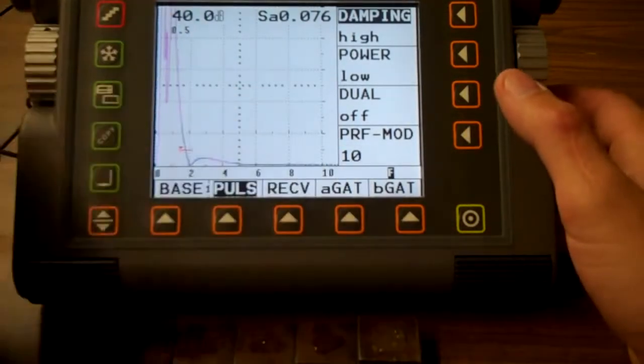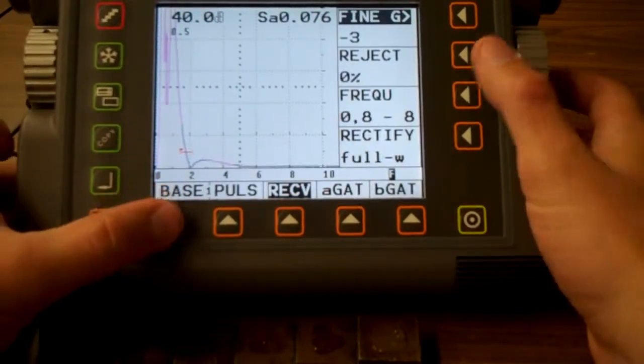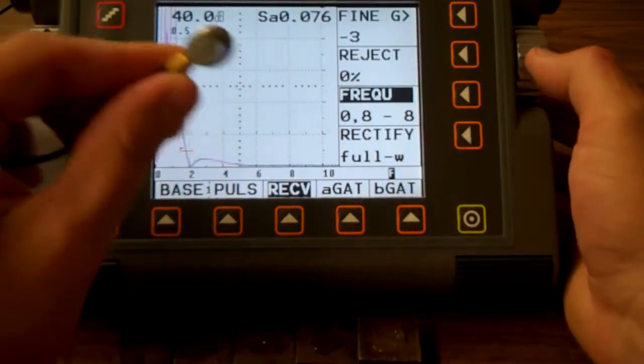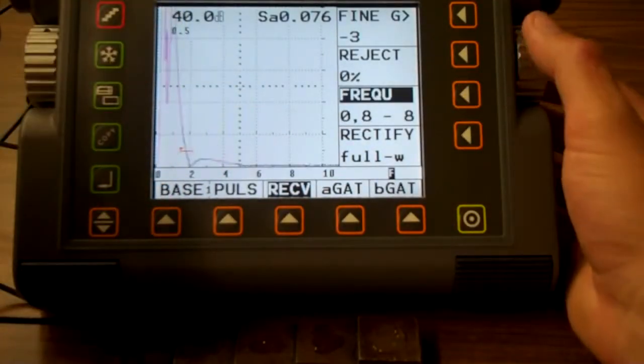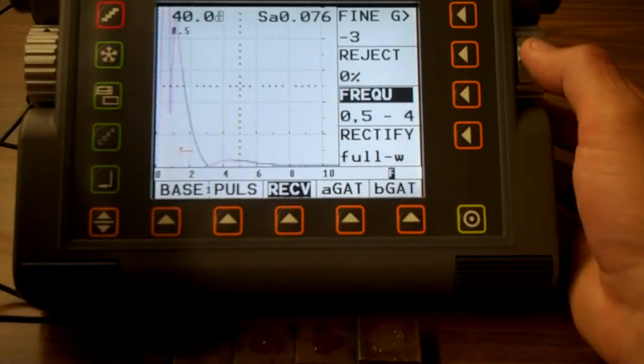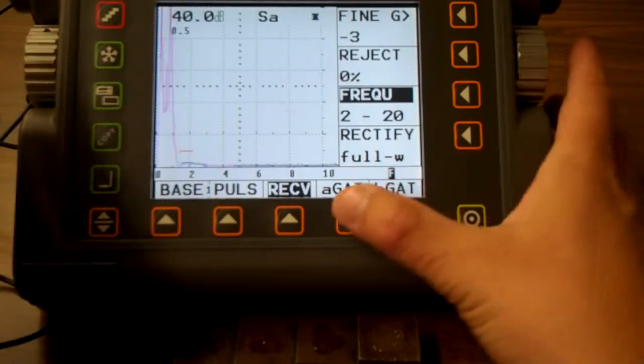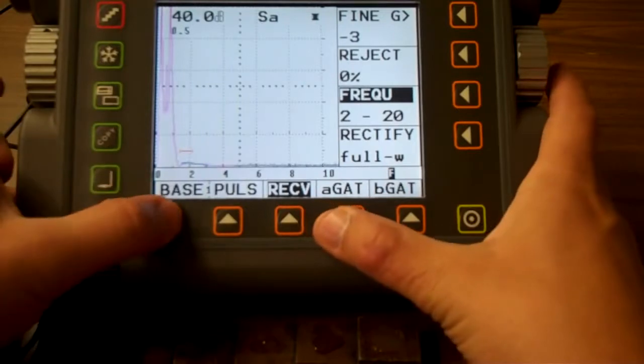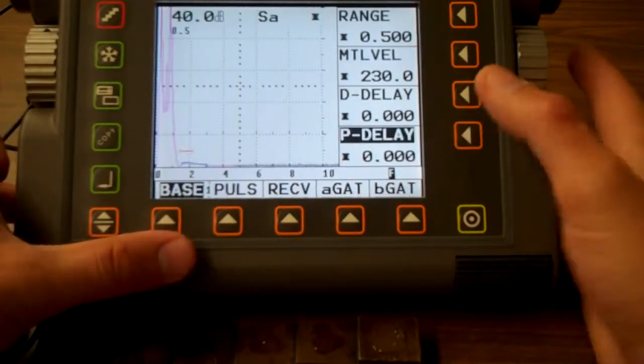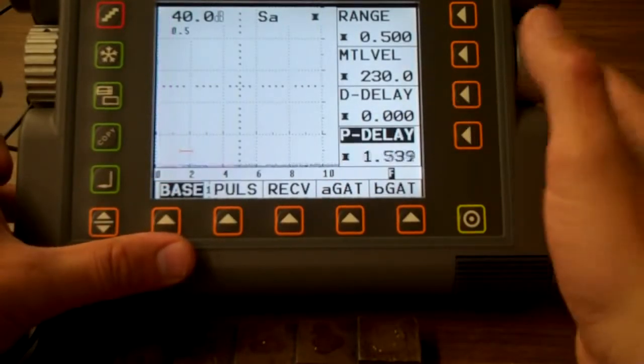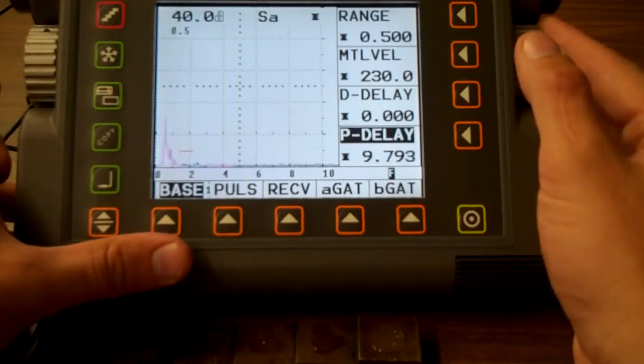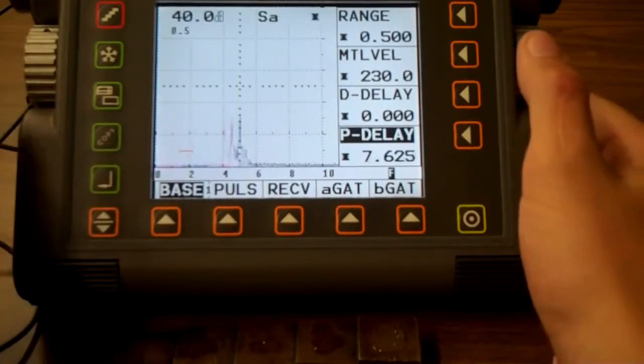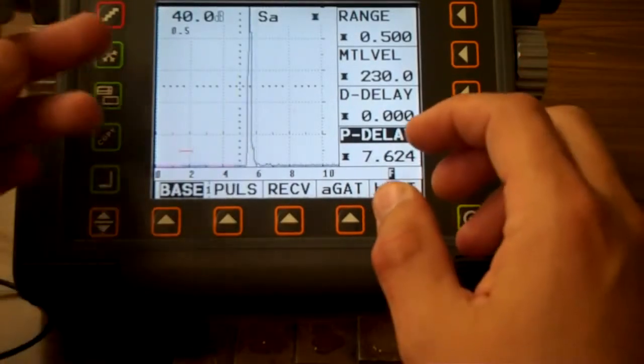I'm going to go to my receiver here, 0.8 to 8. I have a 15 megahertz transducer. 2 to 20, that looks fairly clean. Full wave rectify, that's fine. So I'm going to go back to my base menu. Now I'm going to take my probe delay and push that out. Here's my signal here. Okay, I want to see.